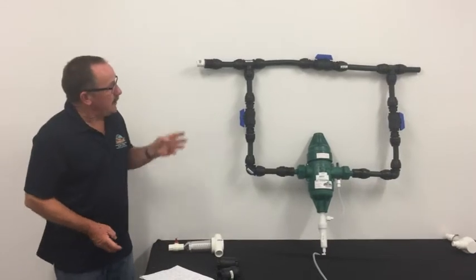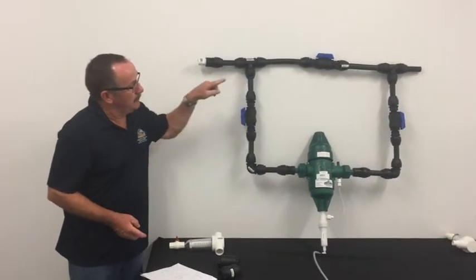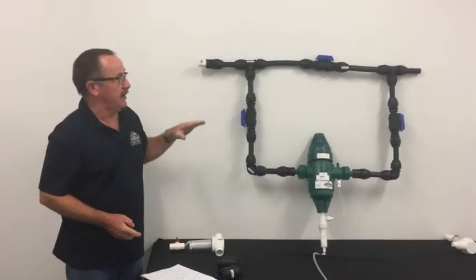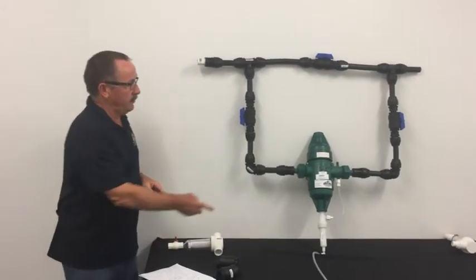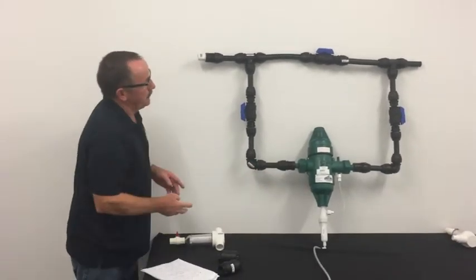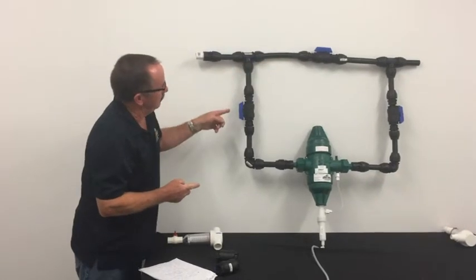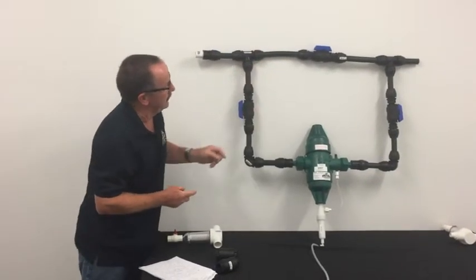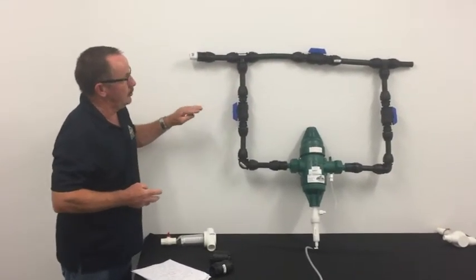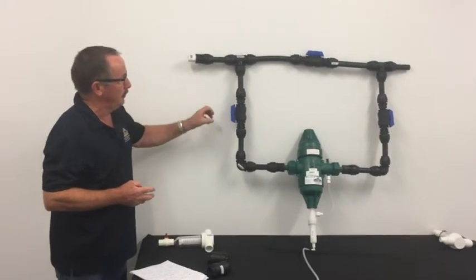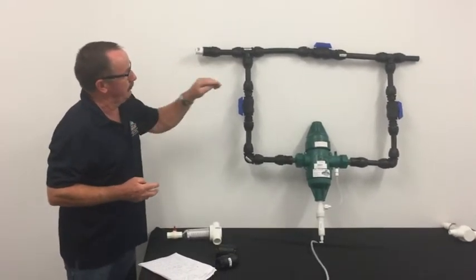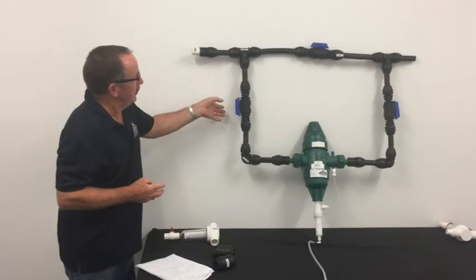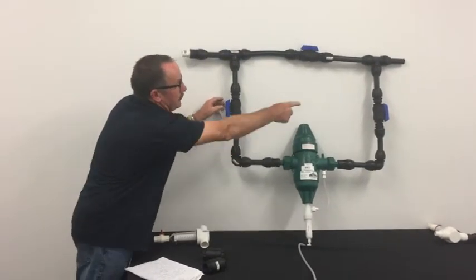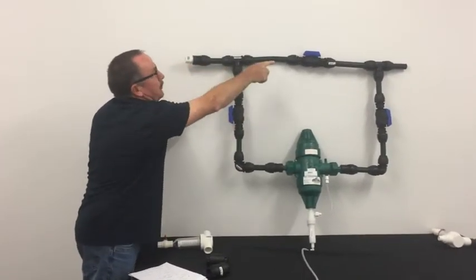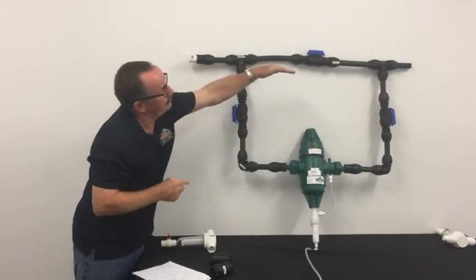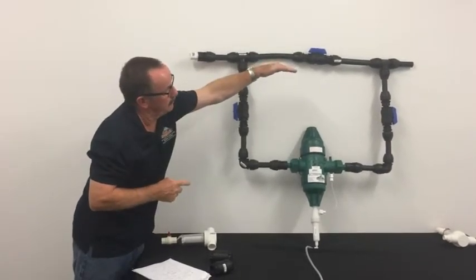Fourthly, it's nice if you can set up the possibility to bypass the whole system. So if this was your doser here, by using a system of 3 ball valves like we've done here, if we want to not have dosed water, if we want to have the water just go directly from the source to the end, we just shut off this valve and the one on the other end, and we open the one at the top, and we allow the water to just go straight through to the animals.